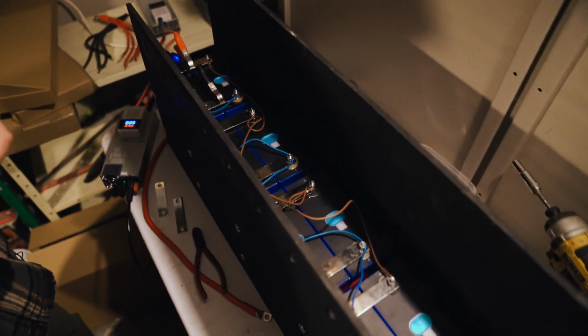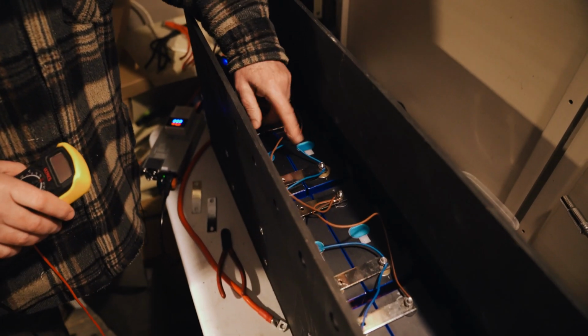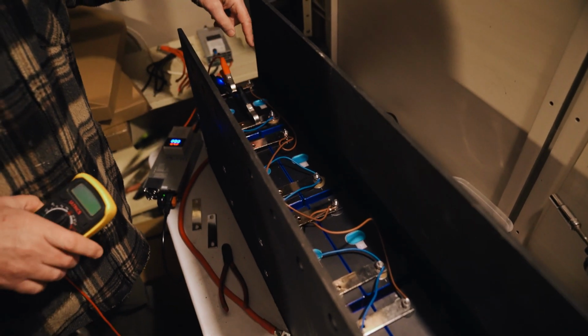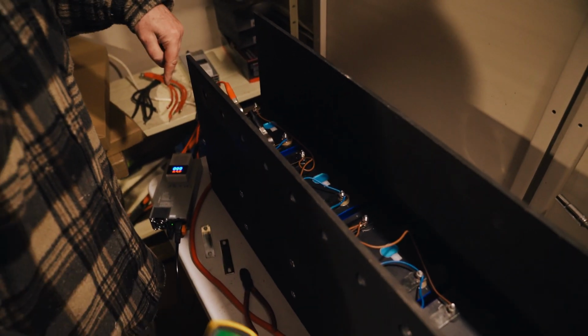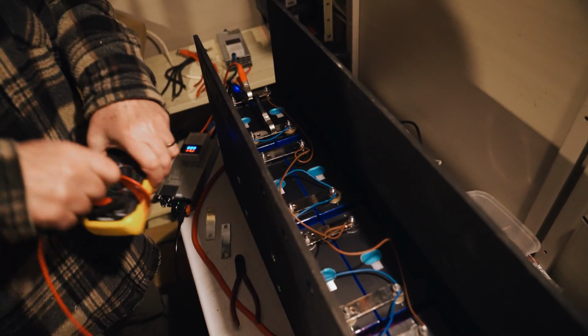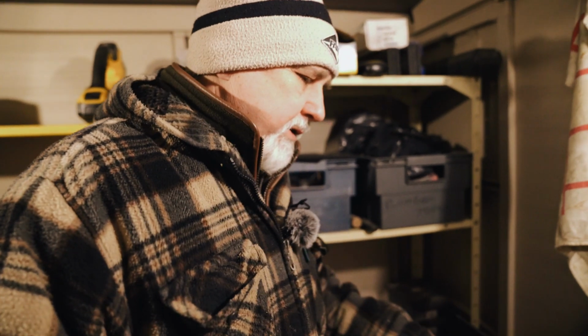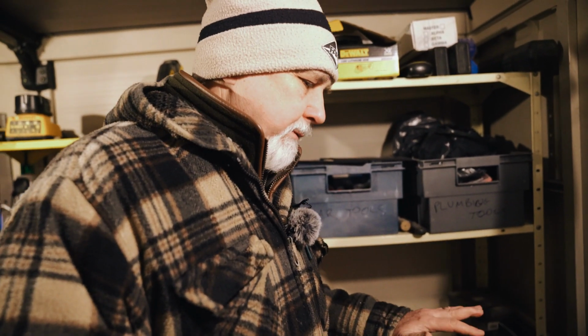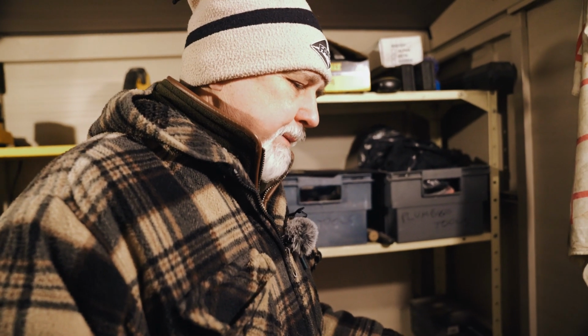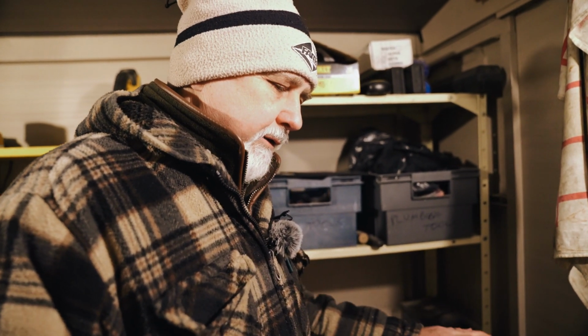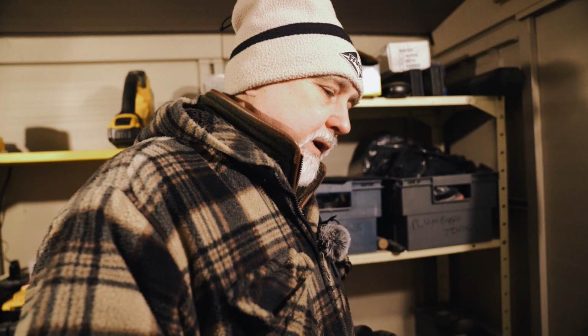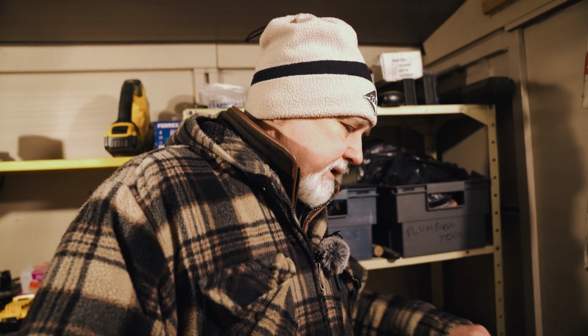So as you can see, we've done the final top balancing using normal household electrical wire. This is 1.5mm wire, and we can set this to a very low current, so we set it at 5 amps and ran it overnight. We had previously charged these up using the normal BMS with the normal charger, at about 60-70 amps, which took about 6 hours or so and brought the whole bank up to nearly 100% state of charge. They're very good, evenly matched cells. So running the 3.65 volt charger at 5 amps was absolutely fine on this household electrical wire.